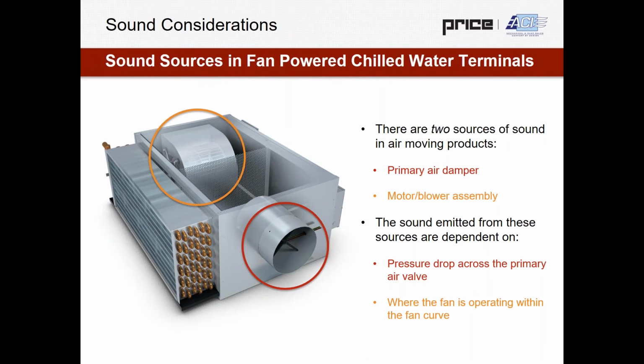Now, the major consideration for this equipment, and the real importance of it, which I think gets overlooked, is the fact that for all intents and purposes, this equipment has a large hole in the side of it, which is leaking that valve noise and that fan noise out of the equipment and into the plenum.